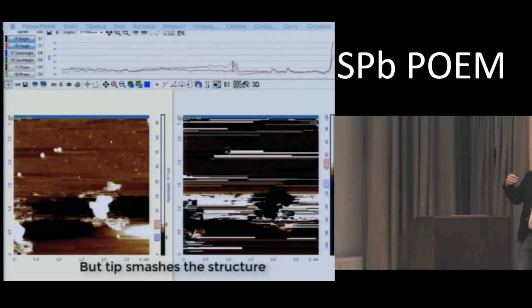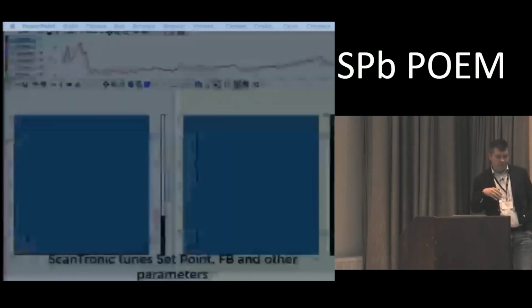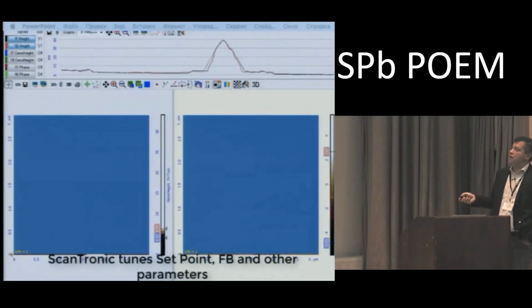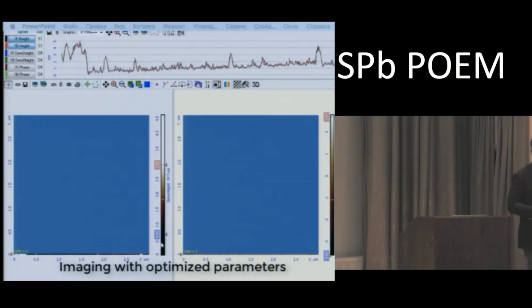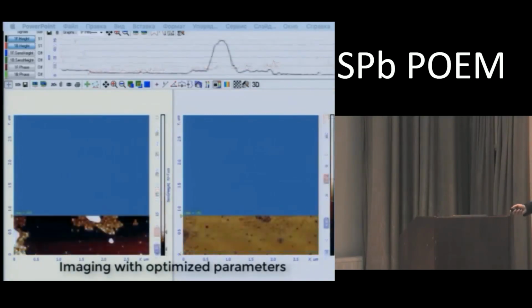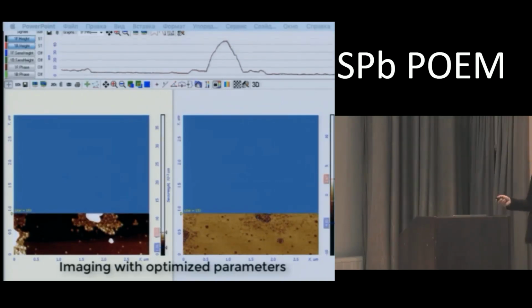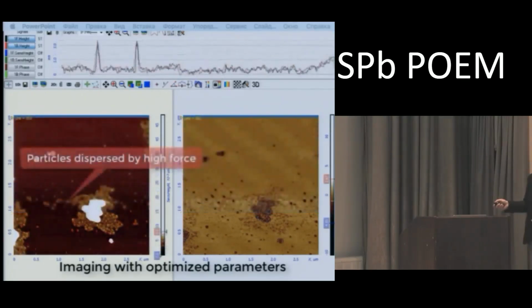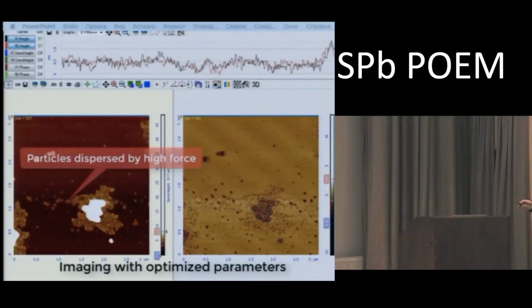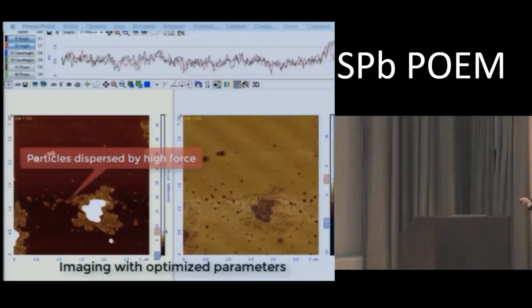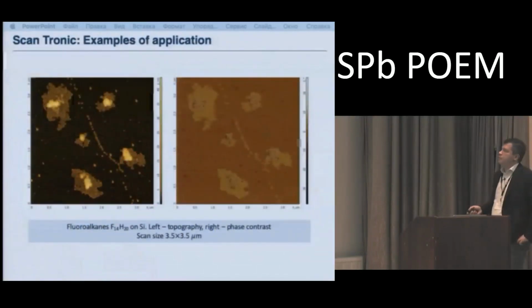But if we take into account all these quite basic things I was talking about, the system can be self-adjusted. And it makes it possible to get the high quality images even on those kind of quite tricky samples. And this is an example. So the scanning parameters and the whole state of the system of the microscope is adjusted automatically here. This is the topography and the phase contrast. And it is even clearer seen that it was damaged during the attempt to manually adjust the parameters.